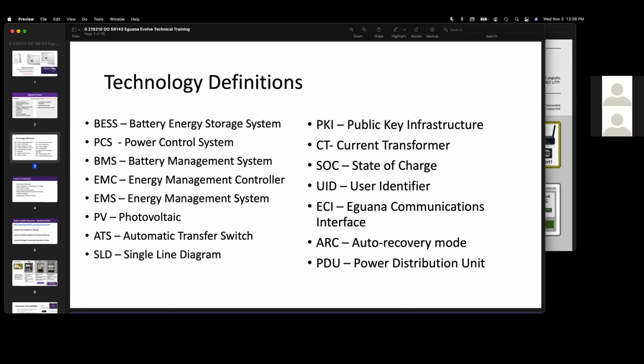DOD, depth of discharge of the battery modules, is technically stated as 100%, but because of battery health maintenance routines, the depth of discharge is limited to, I believe, around 95% maximum. So that's that. Who's the manufacturer of the LFP cells? The LFP modules are manufactured by Pylon Tech. Thank you for your question, Will.